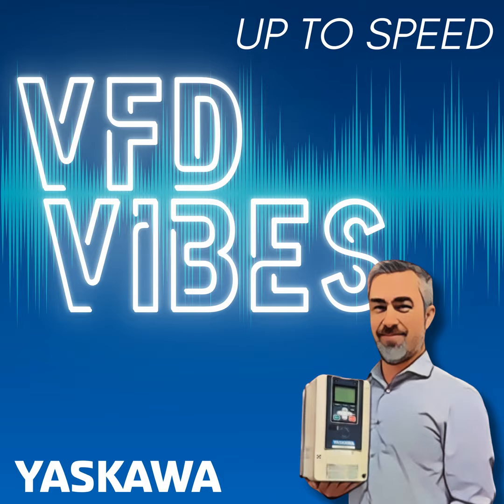Proper installation isn't glamorous, but it's critical. It's like the foundation of a building. If it's off, everything else will be too. Using factory-trained installers makes a world of difference. They know what to look for. Things like high ambient temperatures, long motor leads, and even power factor correction capacitors can cause early VFD failures.